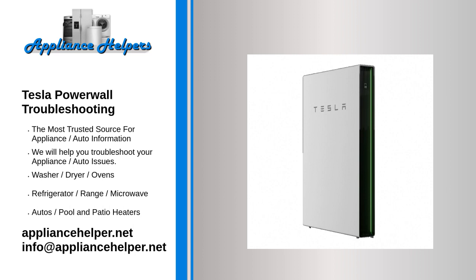Note: turning off the main service disconnect will shut off power for your home. Step 6. Wait no less than 5 minutes to allow your system to fully reboot. Step 7. Turn on the main service disconnect and switch all Powerwall breakers to the on position. Turn on your Powerwall using the power switch, and then turn on your solar inverter. Note: it may take up to 24 hours for the change to reflect in the app.